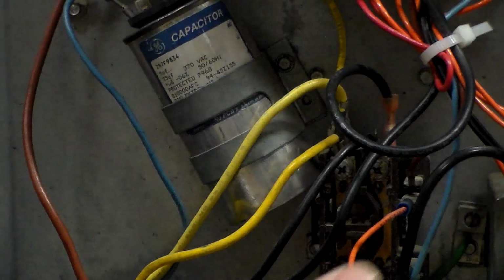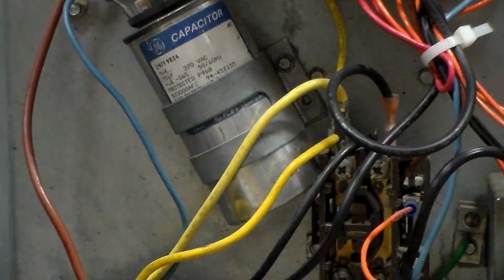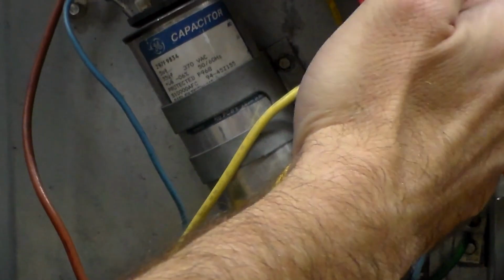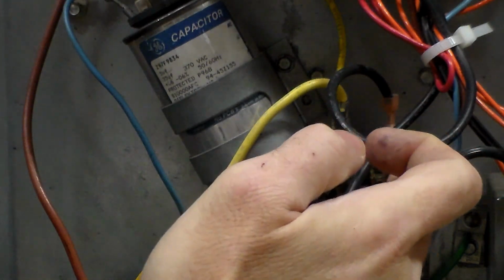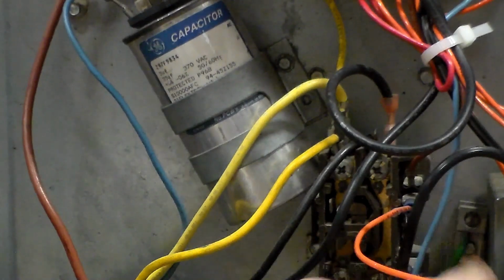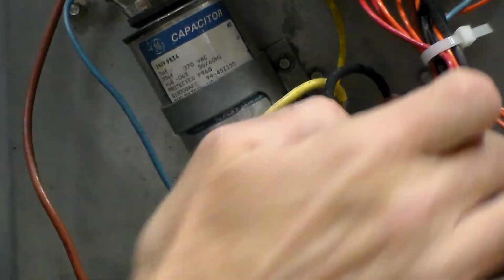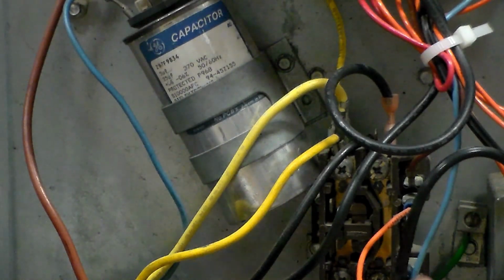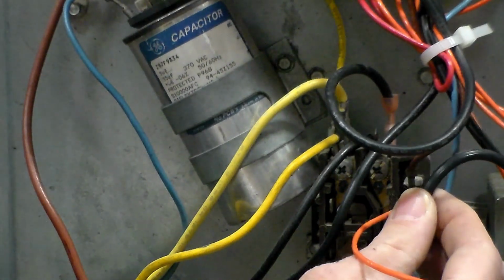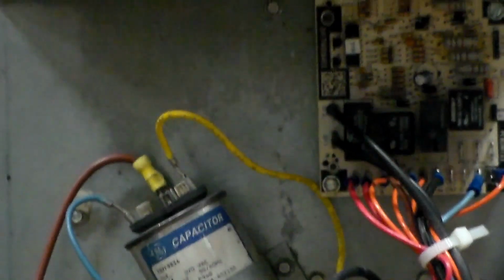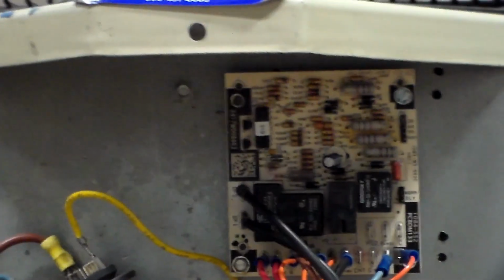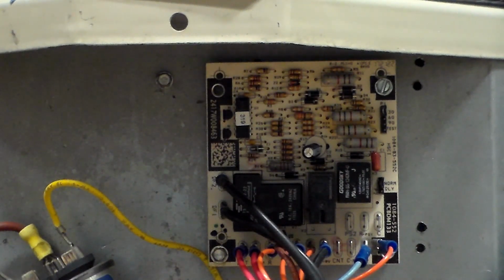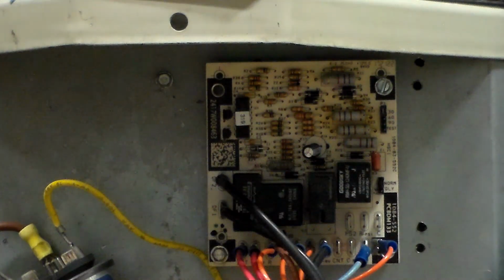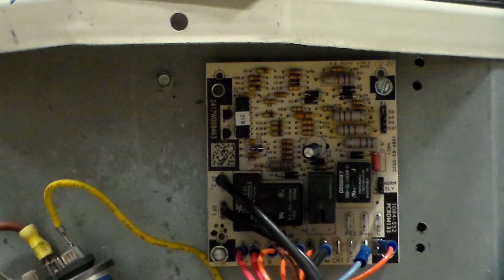And the contactor does the same thing. The board is sending its Y signal down here to the contactor. It only has the one Y, and it's just grabbing all of its commons off the board. The board's common is coming down and linking up here, and then the reversing valve's grabbing it here instead of coming back to the board. Very common. So all we have to do is follow the wires, or the schematic, and it would show us that the O is going to the reversing valve and then coming back to common on the contactor instead of coming back to the board.